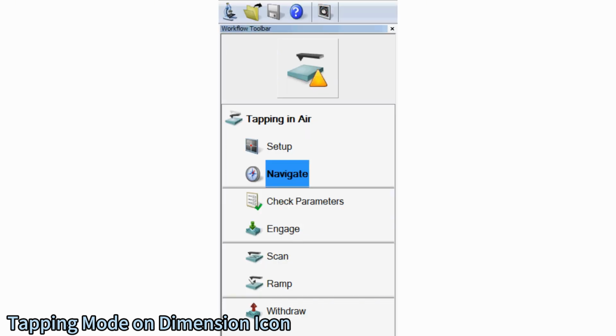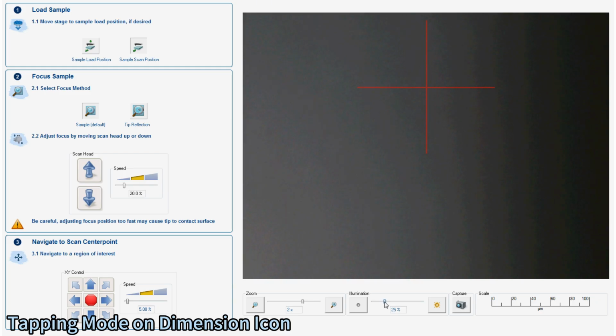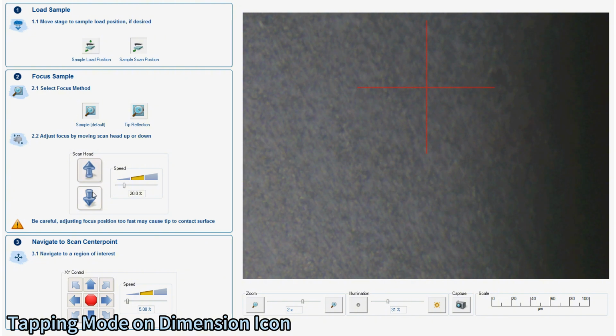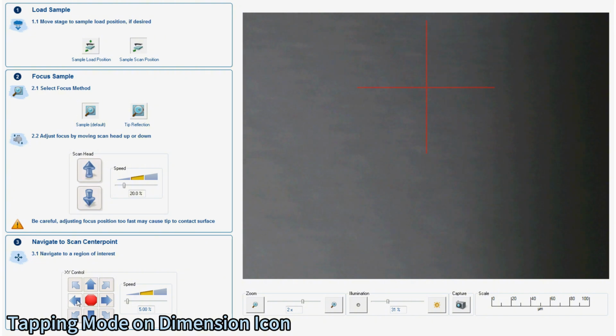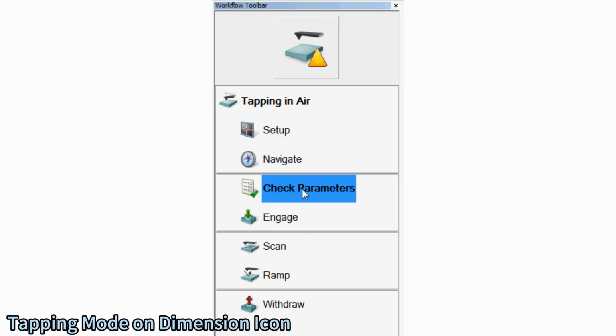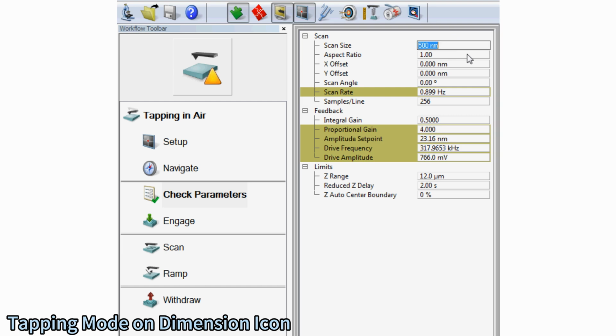Select the Navigate button to shift the focus down to the sample surface and open the stage position controls. Adjust the focus on the sample, zoom as much as necessary, and shift the stage to a position over the sample that is suitable for scanning. Select Check Parameters to open the Feedback and Scan Settings interface. Review parameters such as scan size, rate, and feedback gain values to assure that they are reasonable for the probe type and experiment. Once the scan parameters are satisfactory, initiate the approach by clicking the Engage command.